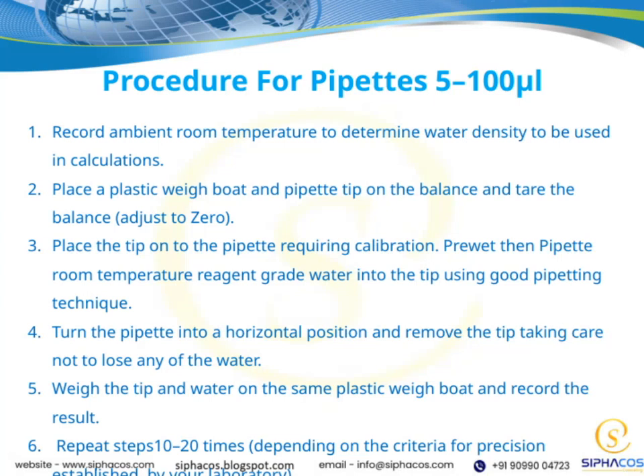Let's start by recording the ambient room temperature, which is important because it helps us determine the water density we'll use in our calculations. Next, place a plastic weigh boat and a pipette tip on the balance and tare the balance to 0. This ensures we're only measuring the weight of the water and the tip. Now, take the pipette and attach the tip, making sure to pre-wet it with the reagent-grade water at room temperature.